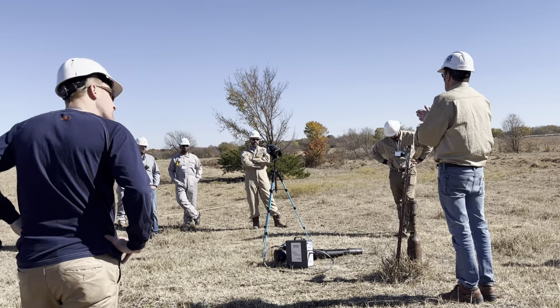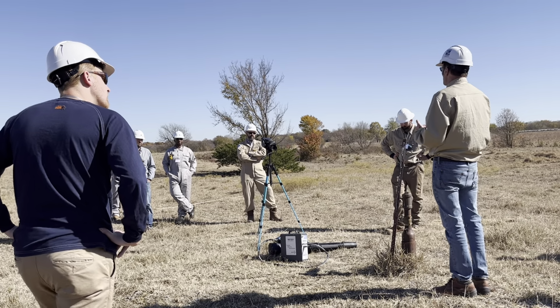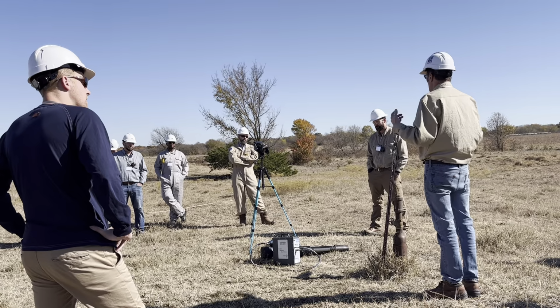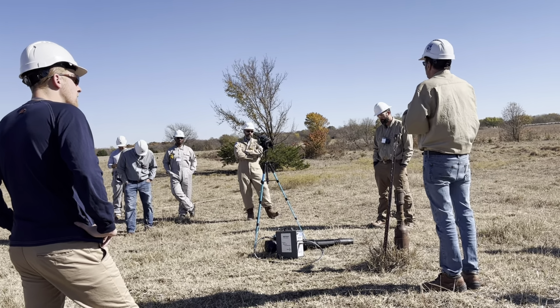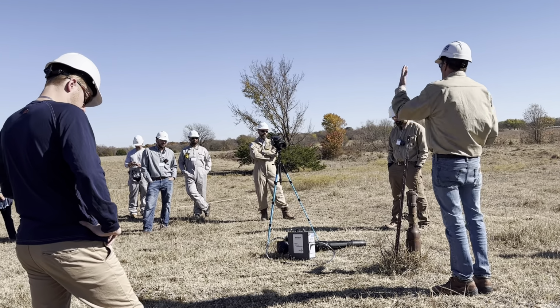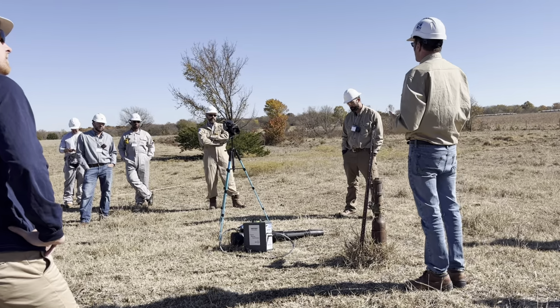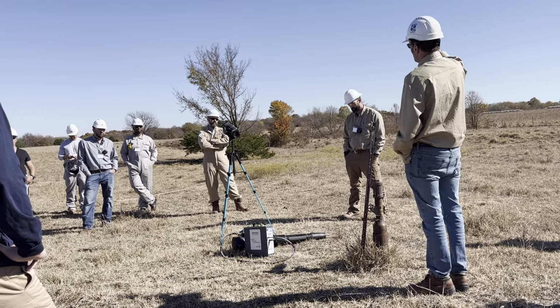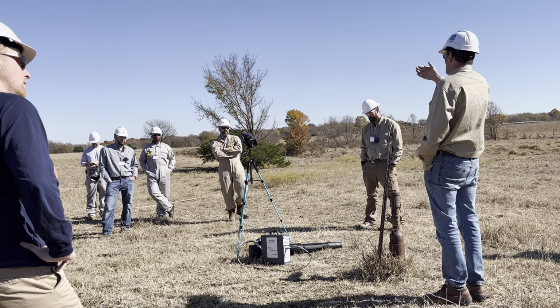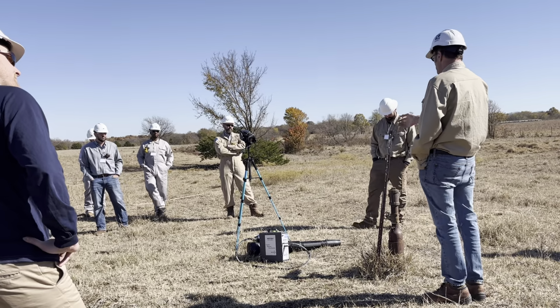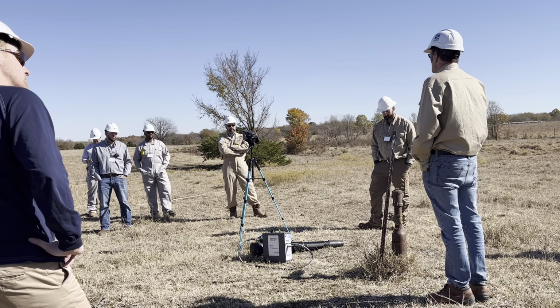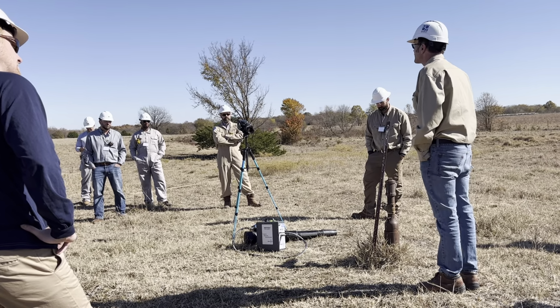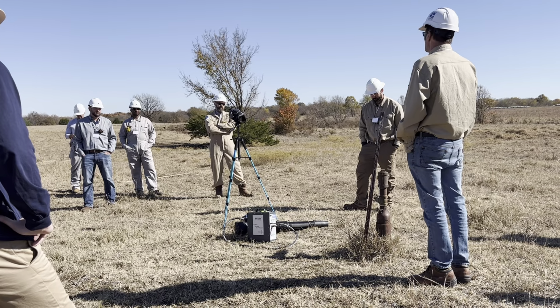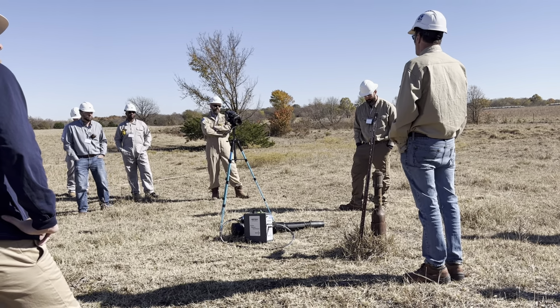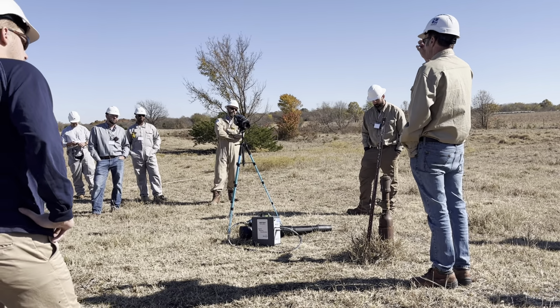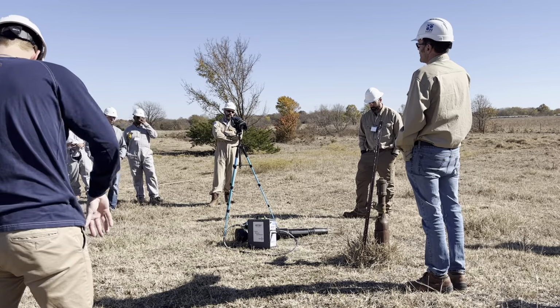So we are recommending audits. I can tell you and I can show you that it doesn't drift from one week to the next. But I'm not going to take on the legal stuff. It'll be down to your own QA procedures, where you say, I want integrity, I want an audit test, maybe weekly or whatever. Then you build up your own QA metrics and say, look, we can demonstrate compliance weekly, now we'll relax it to monthly. A bump gas audit test takes 2 minutes and probably costs $5 in gas. It's not zero, it's probably $5. So we are recommending that you do that, and we're recommending you get it audited once a year, because we like service records, right?